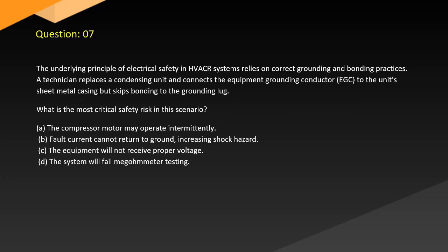Question 7. The underlying principle of electrical safety in HVACR systems relies on correct grounding and bonding practices. A technician replaces a condensing unit and connects the equipment grounding conductor to the unit's sheet metal casing but skips bonding to the grounding lug. What is the most critical safety risk in this scenario? A. The compressor motor may operate intermittently. B. Fault current cannot return to ground, increasing shock hazard. C. The equipment will not receive proper voltage. D. The system will fail megohmmeter testing.